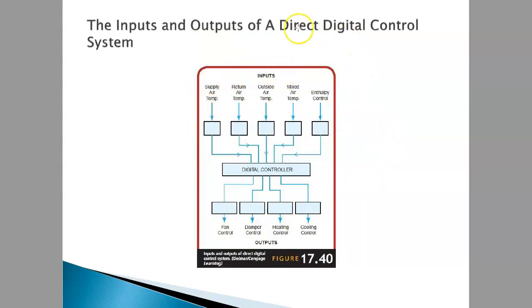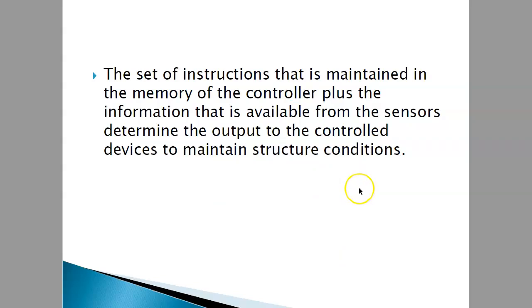This is the input and output of direct digital control. So what are the inputs? Not only direct digital control, but for all controllers. Inputs are supply air temperature, return air temperature, outside air temperature, mixed air temperature, enthalpy control. This is an example. This is all temperature sensors and one also enthalpy control. Direct digital control then processes this and goes to the fan controller to move the fan, to move the damper, and to heat. This is a valve, maybe cooling control. This is a valve, maybe to control the valve, or control the compressor. There is a set of programming instructions that has already been programmed inside the controller. So whatever sensor data is coming in, it will be computed by the controller, and it will determine the output needed and send that to the device or actuator to maintain the room condition or structure condition.